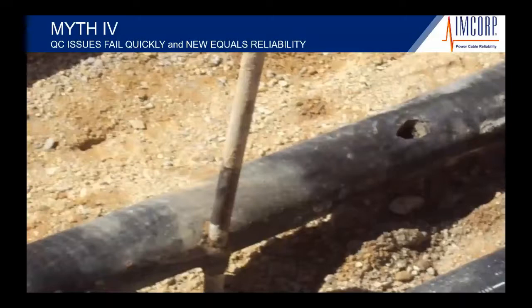Here we have a cable that has been installed, and if anybody can tell, this is a ground rod that's going right through the cable. I was an electrical helper when I first started working, and I did a lot of installing ground rods. We would install these ground rods and one wouldn't go through, so we'd just move it over and find a softer spot. And you can tell where these people tried their first attempt. It didn't go all the way through, so they just moved the ground rod over and went through the cable itself. Now, this cable was in service for a little over 2.5 years.